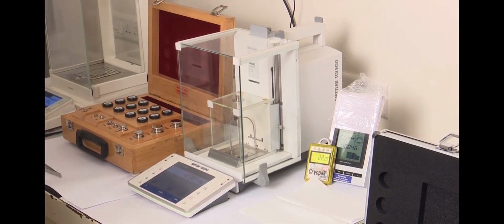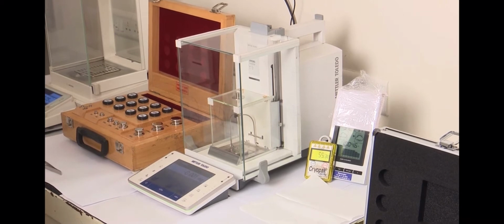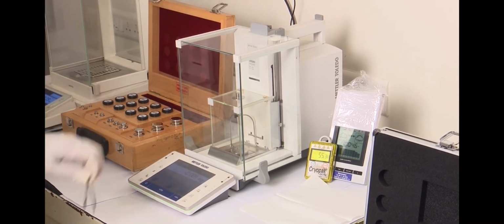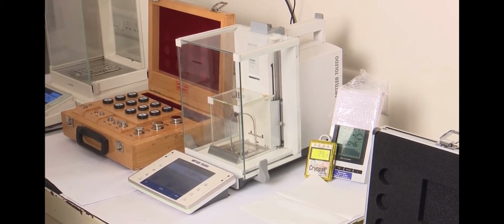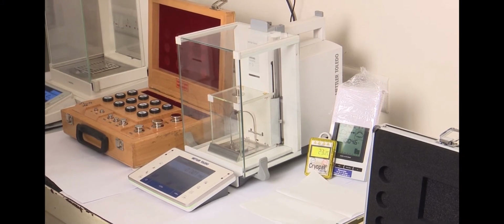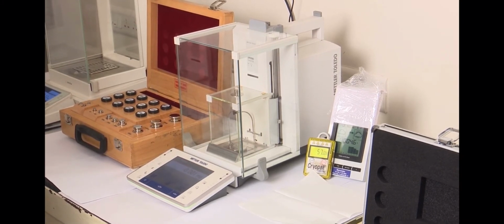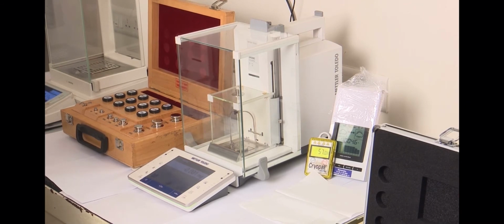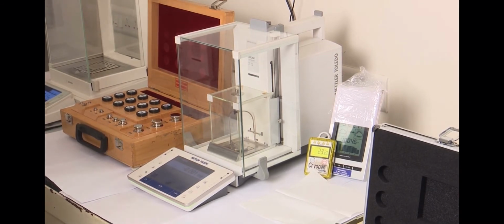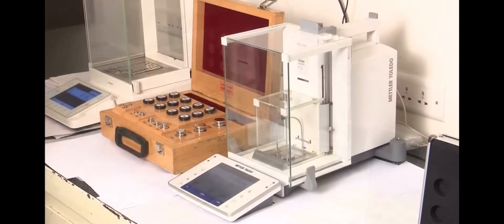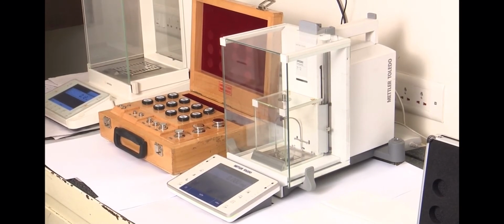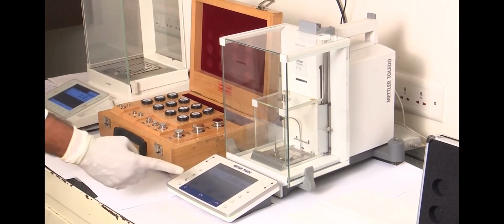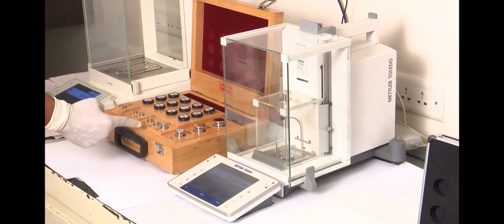Before starting calibration, ensure that the environment condition is maintained. The temperature should be between 23 plus minus 0.5 degrees Celsius. Barometric pressure 1000 plus minus 15 hPa and humidity should be 40 to 60% RH. For calibration, I am using two reference instruments, mass comparator and E1 class reference weight.